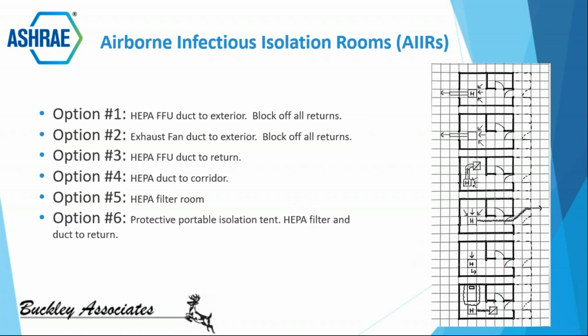Option 3 here, what we're looking at is a fan filter unit again with HEPA filtration being ducted into the return or exhaust of some space. Okay, so this is difficult in some spaces. It usually requires some existing exhaust or return system. This scenario should really only be used if ducting to the exterior is not a viable option. And the other thing that always comes up when we're talking about this is if this is a variable air volume system, we're basically going to open another Pandora's box of problems as pressurization is going to become infinitely more difficult. So try to avoid this, but again, this is where ASHRAE is ranking this option in a temporary facility.